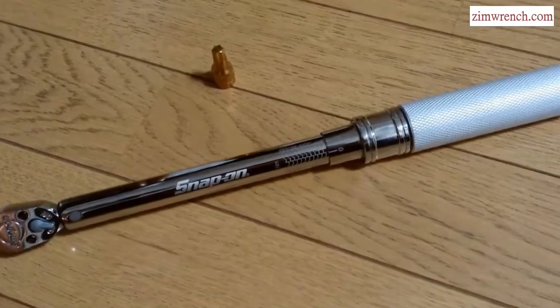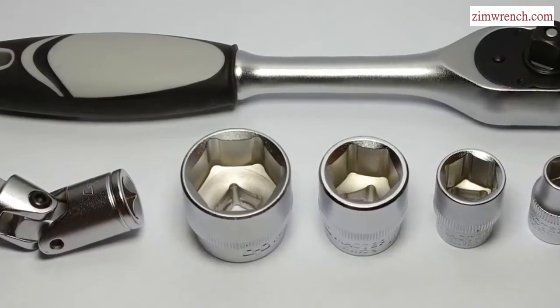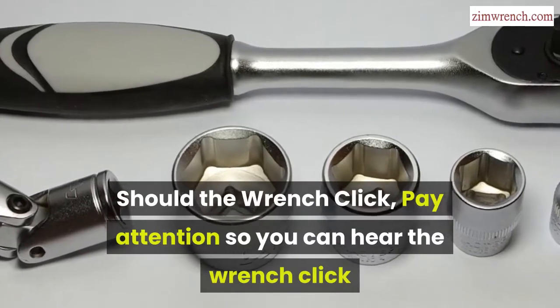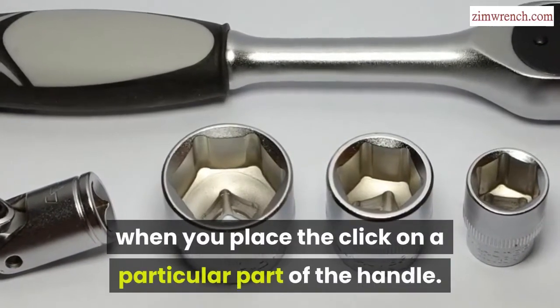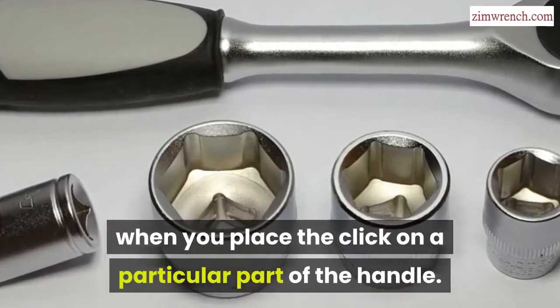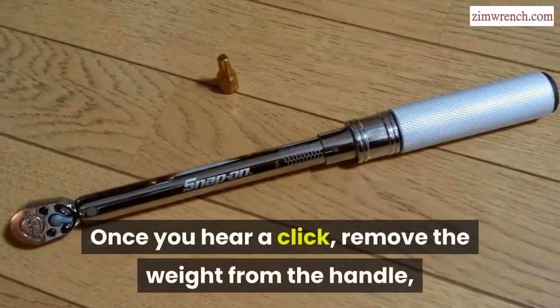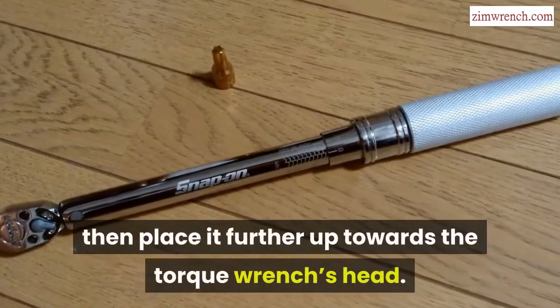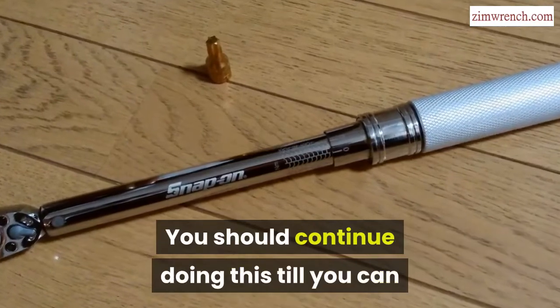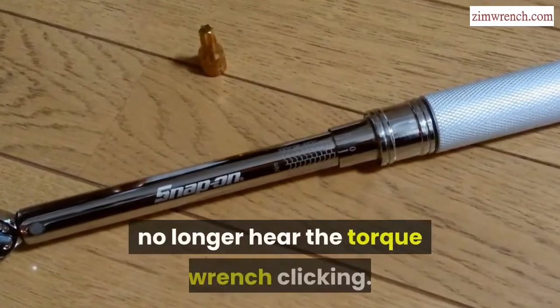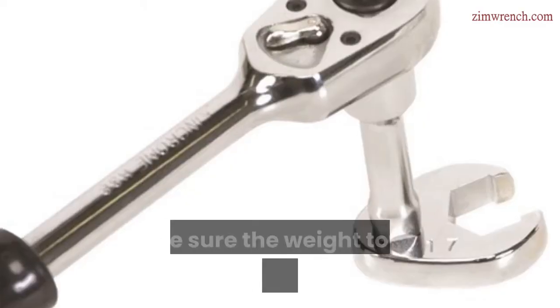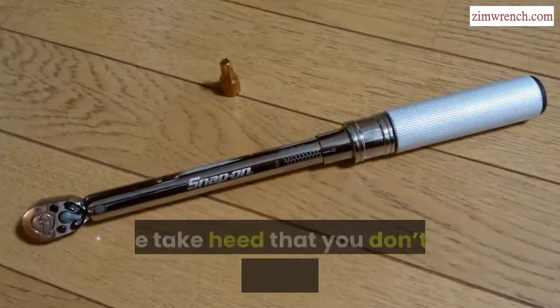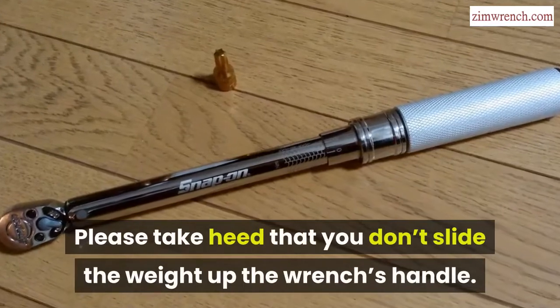Adjust the weight on the handle. Should the wrench click, pay attention so you can hear the wrench click when you place the weight on a particular part of the handle. Once you hear a click, remove the weight from the handle, then place it further up towards the torque wrench's head. You should continue doing this till you can no longer hear the torque wrench clicking. Make sure the weight is totally lifted off the handle and set down once more. Please take heed that you don't slide the weight up the wrench's handle.